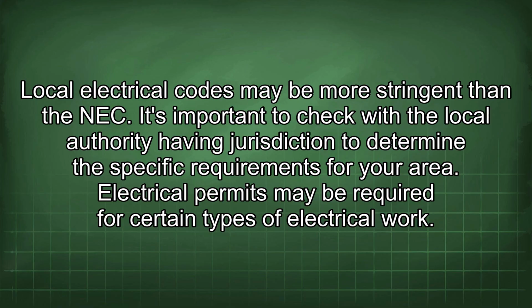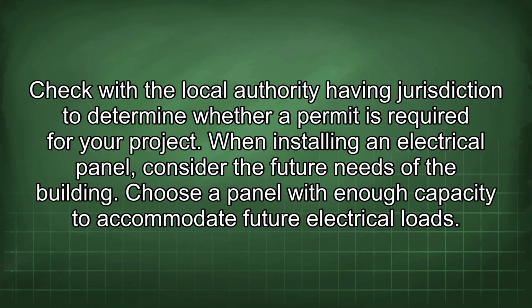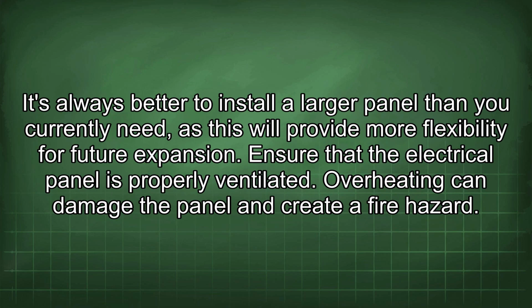Electrical permits may be required for certain types of electrical work. Check with the local authority having jurisdiction to determine whether a permit is required for your project. When installing an electrical panel, consider the future needs of the building. Choose a panel with enough capacity to accommodate future electrical loads. It's always better to install a larger panel than you currently need, as this will provide more flexibility for future expansion.